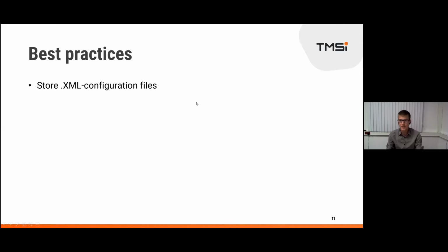It has been a repeating subject already in this webinar, but it's very convenient to store your configuration in XML files, especially if you're working together with some colleagues on different experiments. It's easy that you would have your own configuration stored, can directly load it into the device, and you don't have to do any adaptations anymore. So that makes it quite user-friendly to have a quick setup for your measurements.